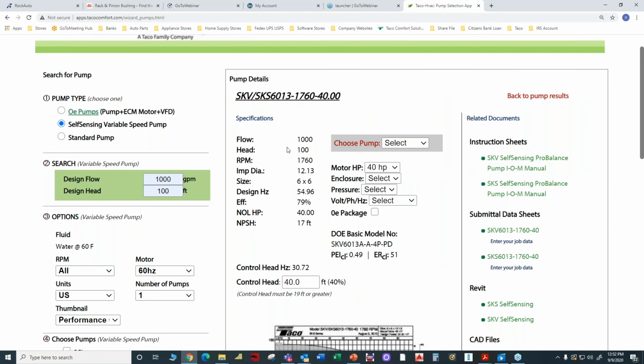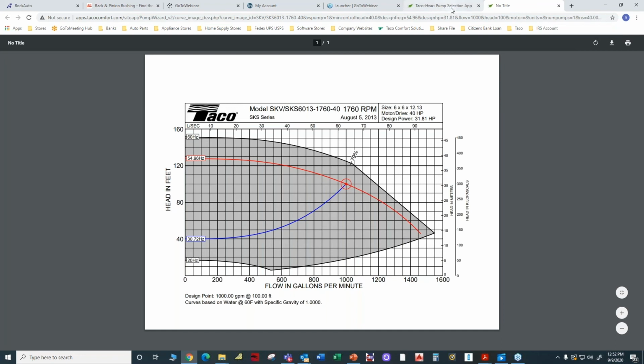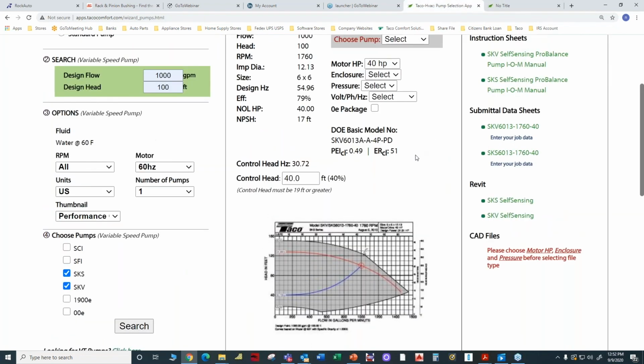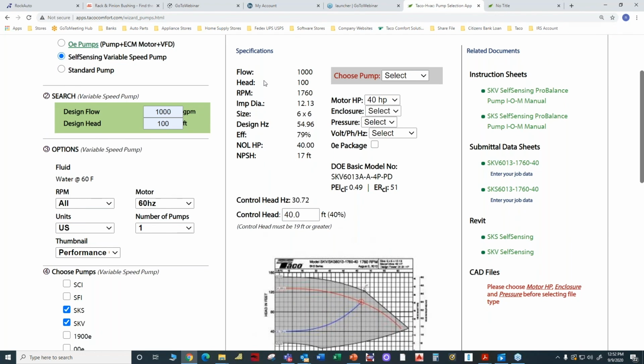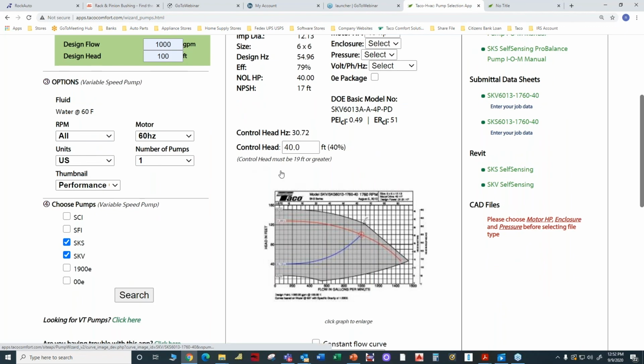Now, I'm going to click on this. The default for the control head is 40% of the design head. So we at the factory, if you don't tell us what you want for control head, will pick one, and we will pick it based on 40% of the design head. In this case, the design head is 100 feet. 40% of that is 40 feet. Now we can pick any value greater than 19 feet, because anything less than 19 feet results in a speed of less than 20 hertz, and we don't want the pump to drop below 20 hertz.